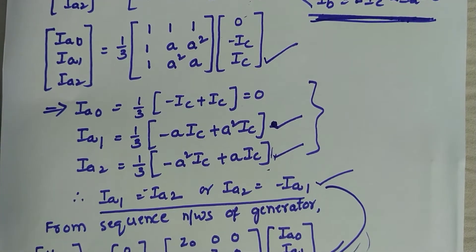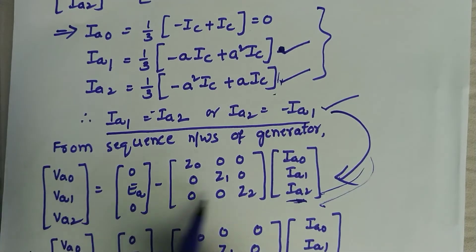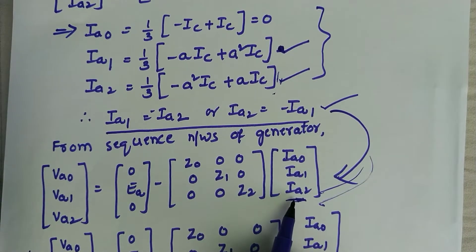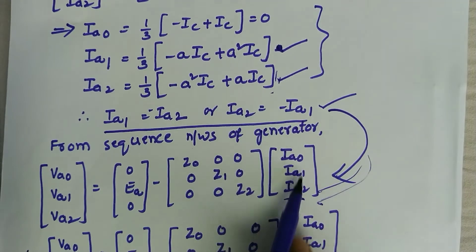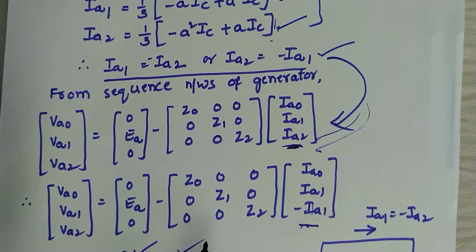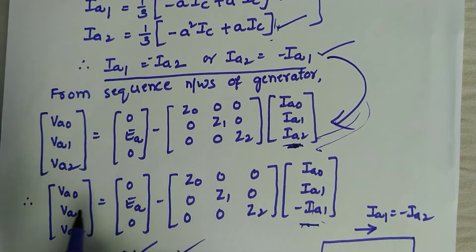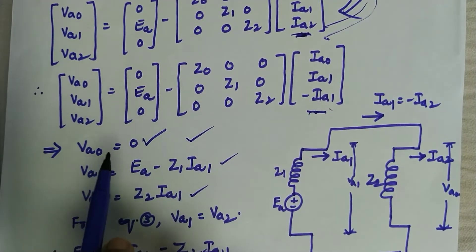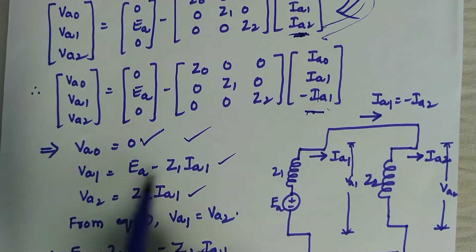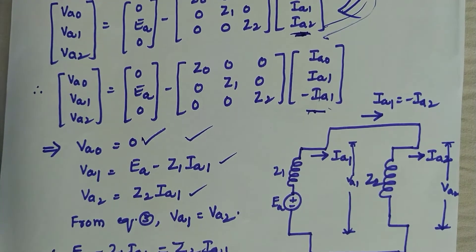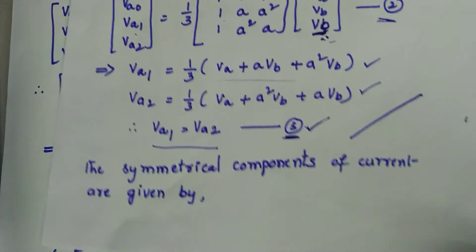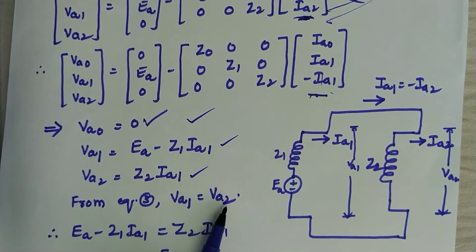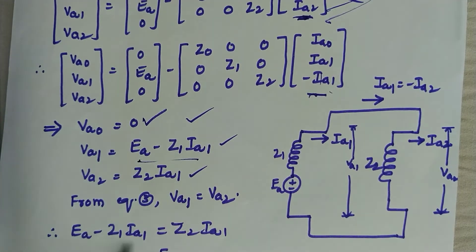Now we consider the sequence networks of the generator. Substituting the condition Ia2 equals minus Ia1 into the sequence network equations and converting to normal equation form, we get Va0 equals 0, and relations for Va1 and Va2. The third equation gives Va1 equals Va2.